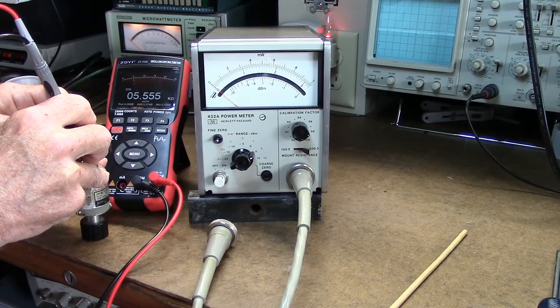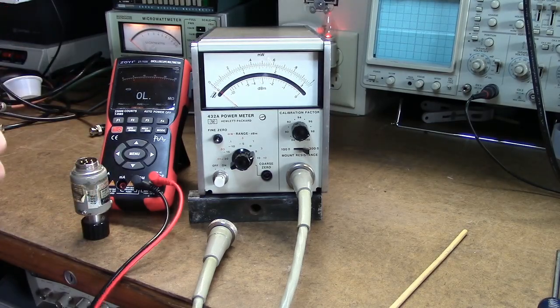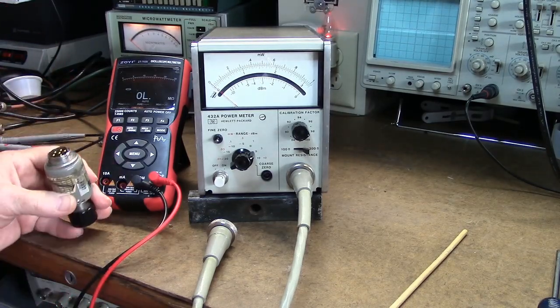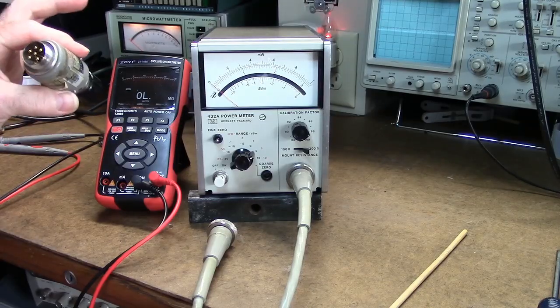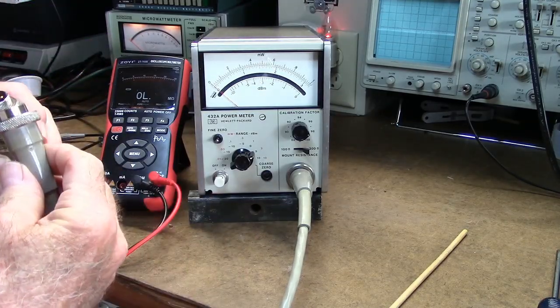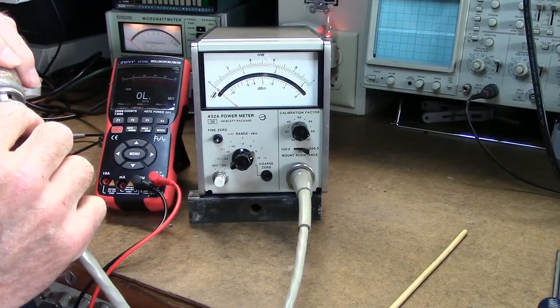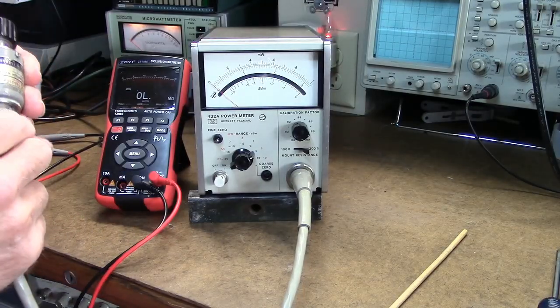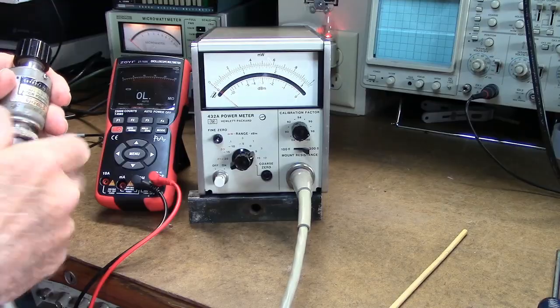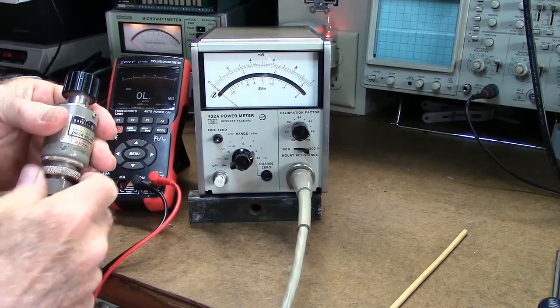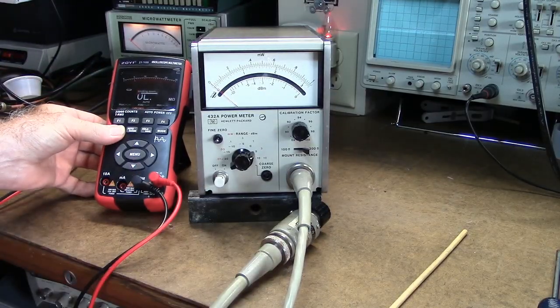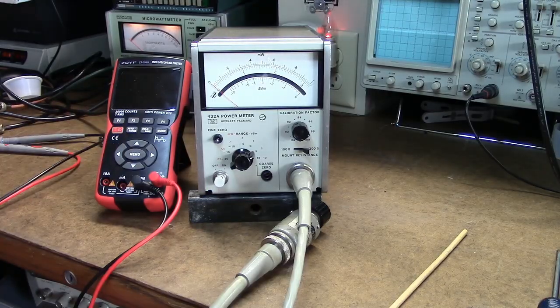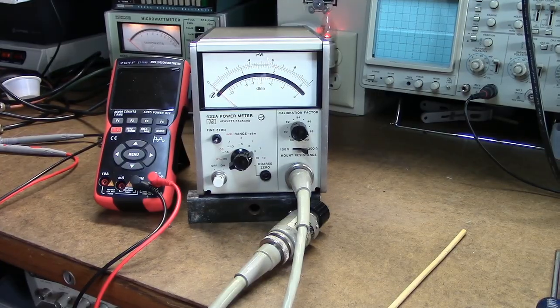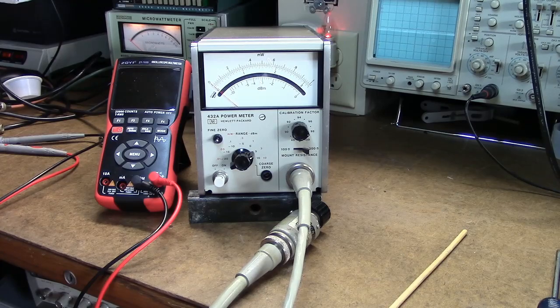Pretty close. Okay, so I've determined that the two thermistors are intact, so that's a good sign. And then of course this connects to the cable, and you're ready to take your measurements. So if you get at the Hamfest and you get one of those thermistor mounts and they measure open circuit, you might want to just forget it because it's no good. Anyway, that's just a tip.